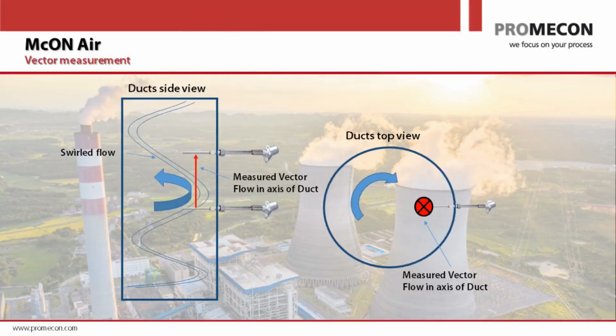So another big advantage. Or here, we look at that, we have the typical swirled airflow between the two sensors. This swirled flow does not affect our sensors because the distance vector between the two sensors is perfectly in line with the axis of the duct. So in this case, no impact.